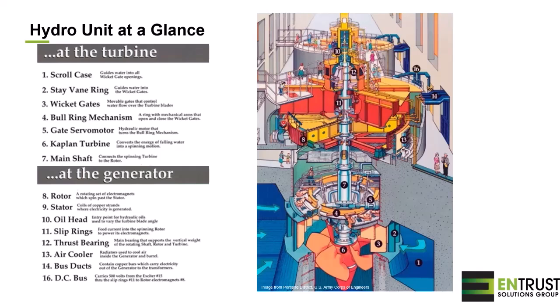To keep the generator cool, because there's a lot of energy being dissipated in thermal energy, we will find a cooler, air cooler or water cooler here. And all the weight of the turbine and generator rotor is taken by the thrust bearing that we find at this level. Usually it's on top or just below the generator. And so that's the main component of a hydro turbine and generator.